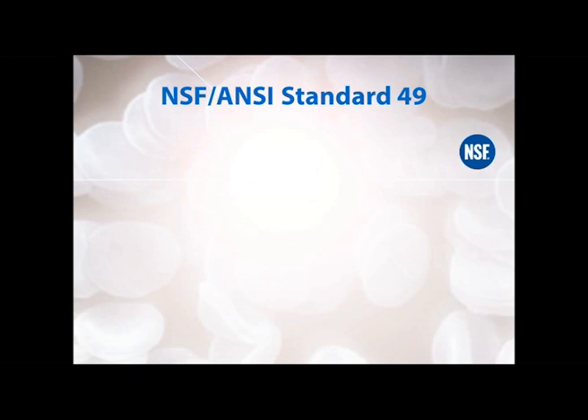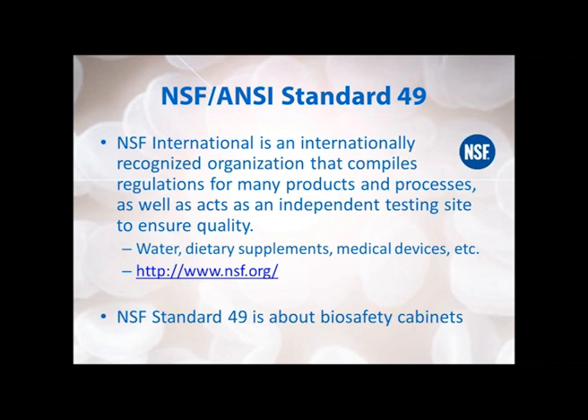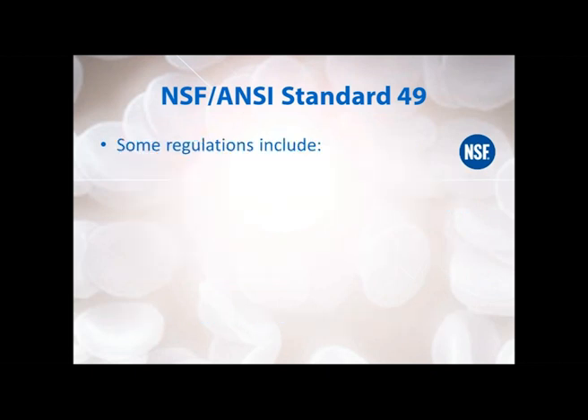In order to understand where these results and tests come from, we're going to discuss a little bit about NSF ANSI Standard 49. NSF is an internationally recognized organization that compiles regulations for many products and processes and also acts as an independent testing site to ensure quality. They do a lot of water testing, which is their main product, but they also test dietary supplements and medical devices. NSF Standard 49 is about biosafety cabinets, and some of the regulations included are that there's no intake air allowed below 100 feet per minute.